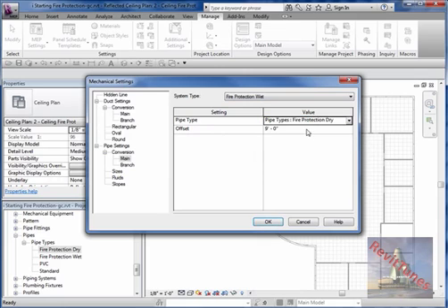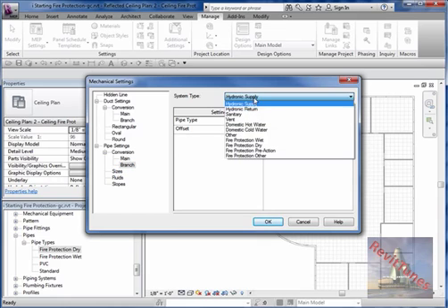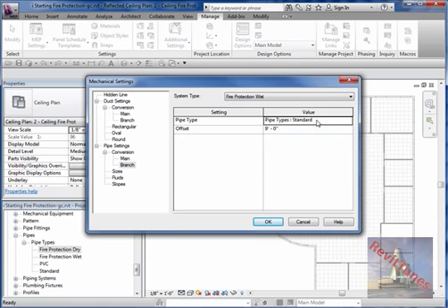The pipe we created, fire protection wet. And we are saying by default always put it 9 foot above whichever level we are working in, floor 1, floor 2, floor 3, whatever, it will be 9 foot above. So we are assuming the ceiling is an 8 foot ceiling and our pipe is at 9 foot height. Now for branches, also we are going to do the settings for wet system. And for wet system, we are going to use wet pipe and 9 foot offset. So we have settings for main wet or branch wet system. We have selected the setting. Say OK.